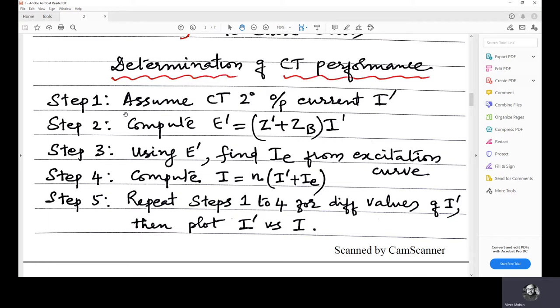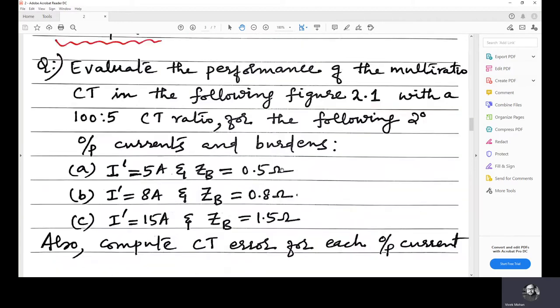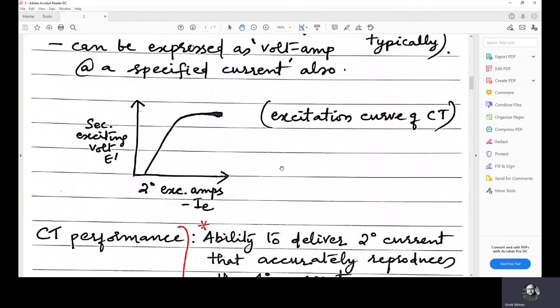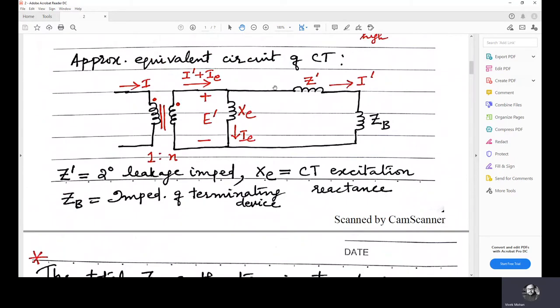In step two, we compute e', the secondary voltage. e' is equal to (z' + zb) into i', where zb is the impedance of the sensing device or the relay, and z' is the leakage reactance from the equivalent circuit. From the equivalent circuit, z' is the leakage reactance and zb is the burden or the impedance of the sensing device.